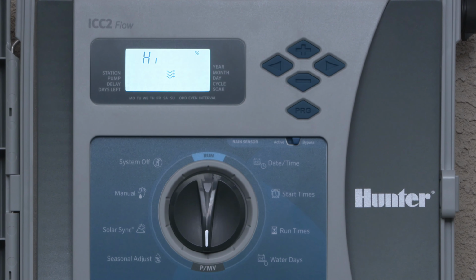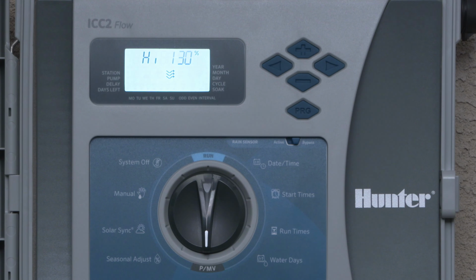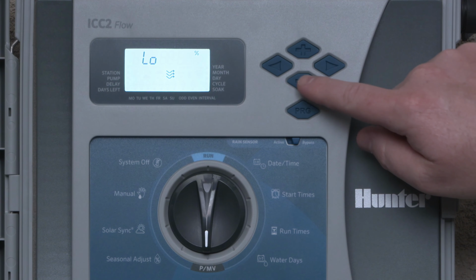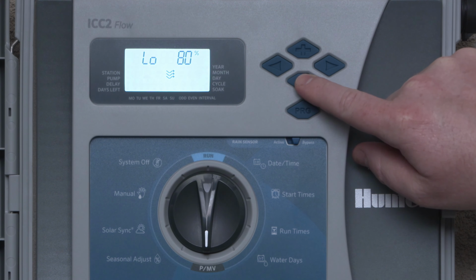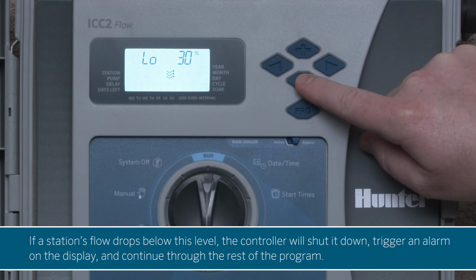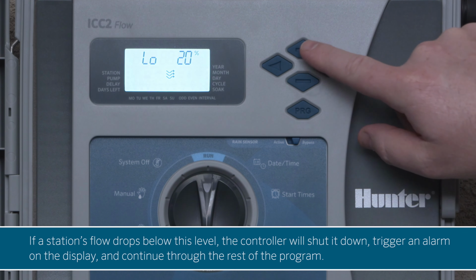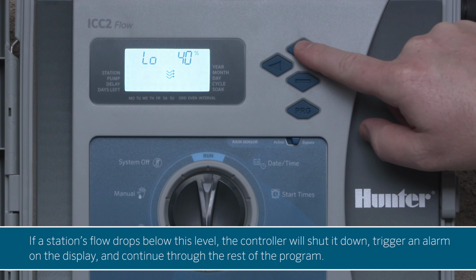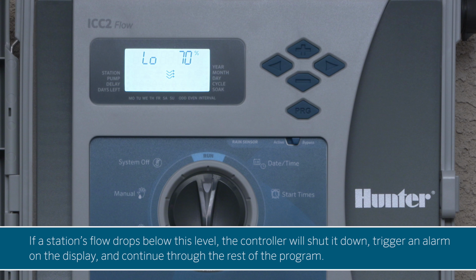To set the low flow shutdown threshold for each station, press the right arrow button. Use the plus and minus buttons to select a percentage between 20% and 90% of normal flow. If a station's flow drops below this level, the controller will shut it down, trigger an alarm on the display, and continue through the rest of the program.